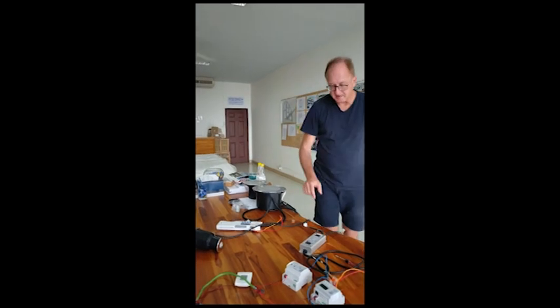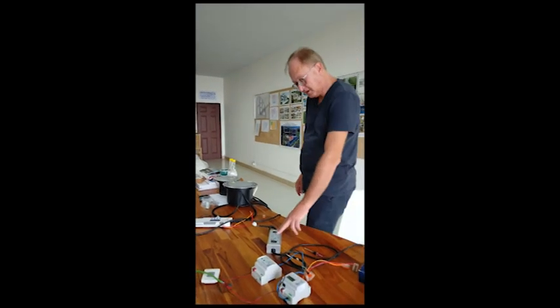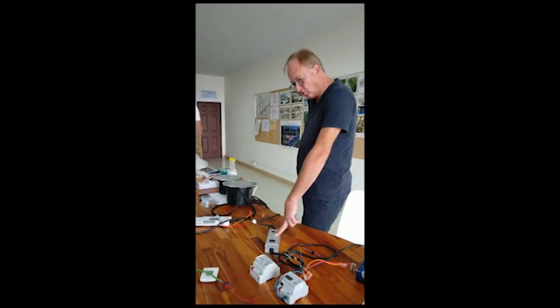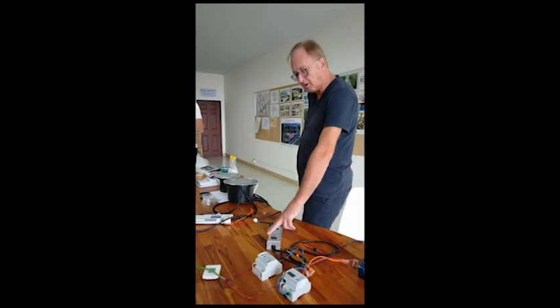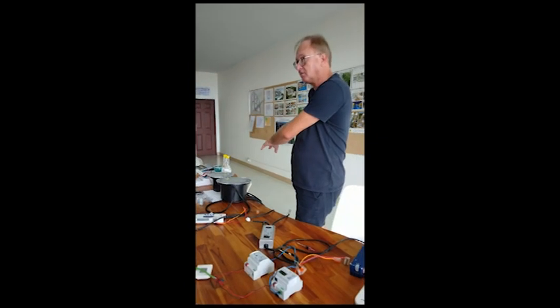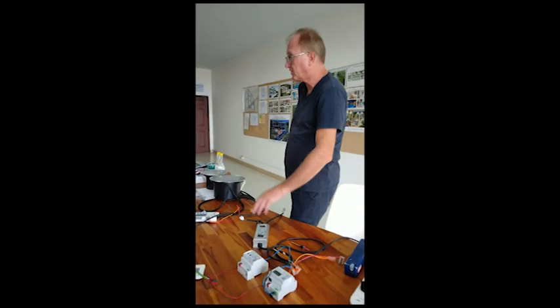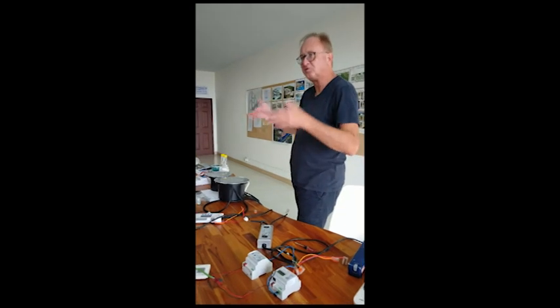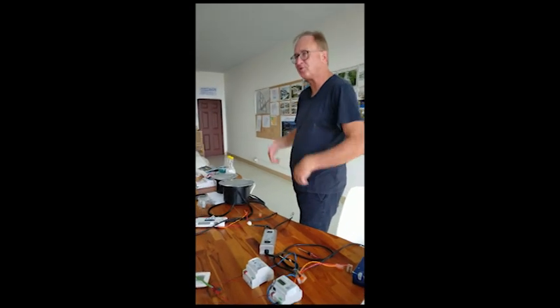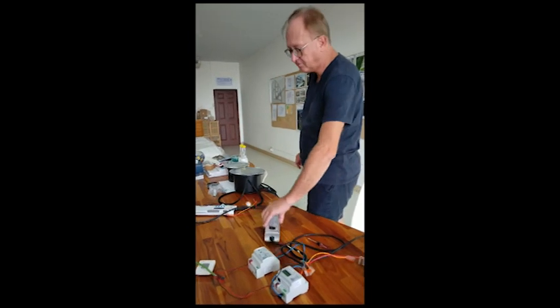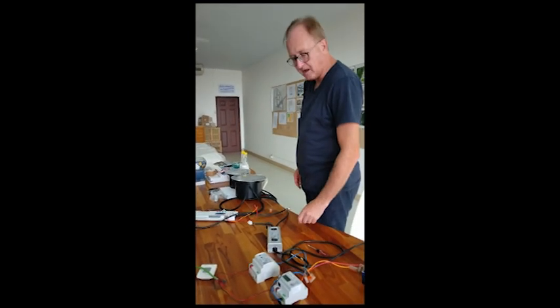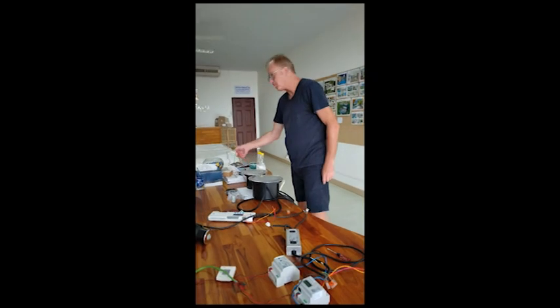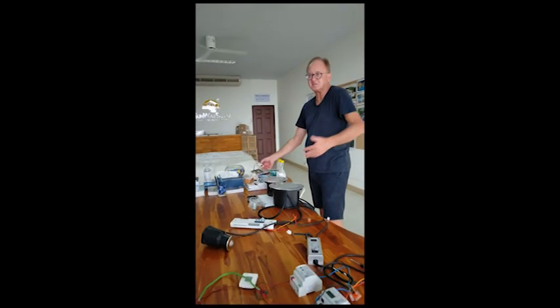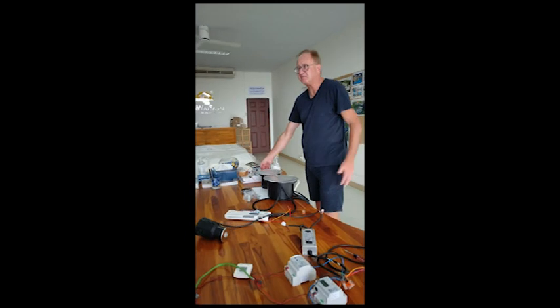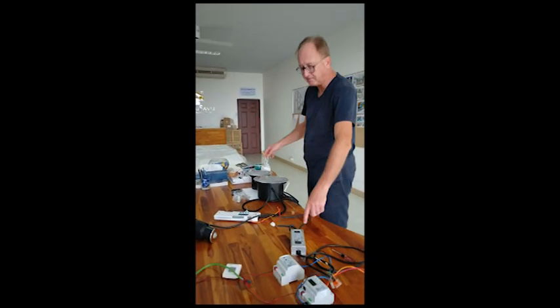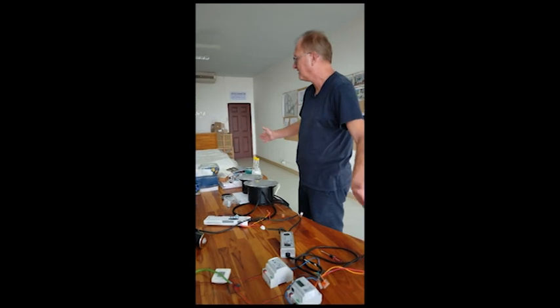What an advantage you have here is that you don't need one power transformer for each light group. If you have one room with, say, 200 watts split into 4 or 5 light groups, you can use one 200 watt unit and distribute them in between. As long as the total ampere is there, I'm fine. So I don't need one by one, otherwise we'd have too many of these devices.